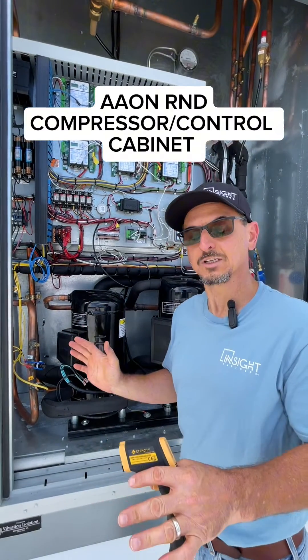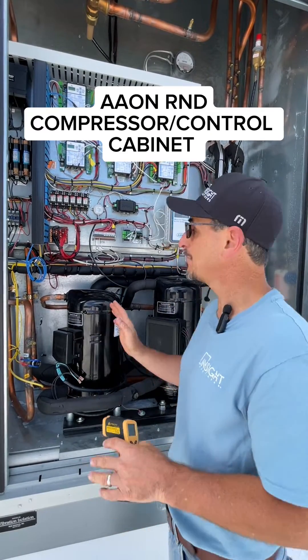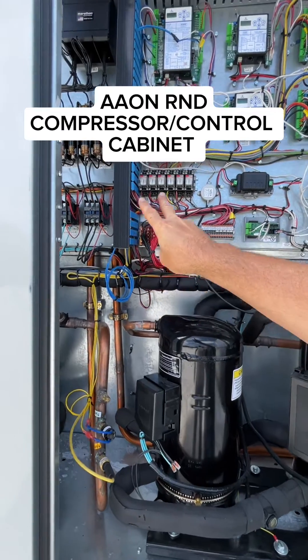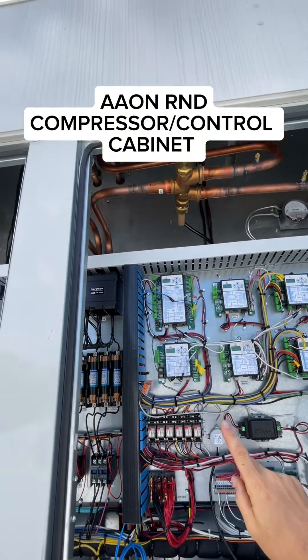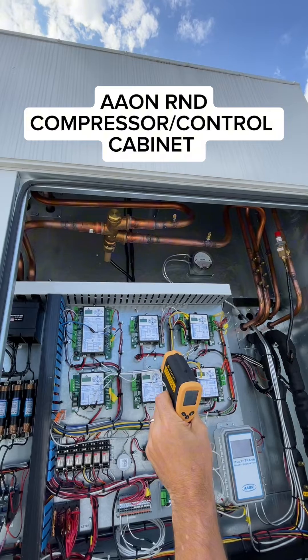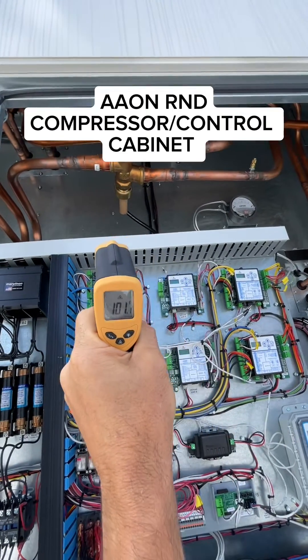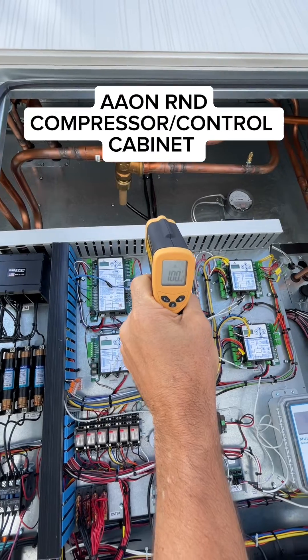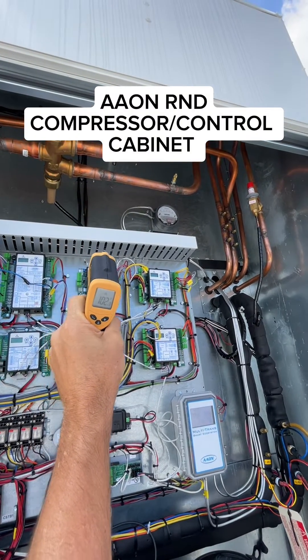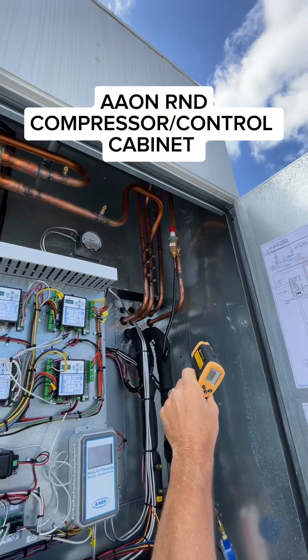The interesting thing about AAON units is most of them, especially makeup air units dealing with some type of dehumidification, have a modulating hot gas reheat valve. This is a great example — you can follow the discharge gas line. These two lines for both circuits go up behind the controls and high voltage panel area. This is the three-way valve here. You can see the temperature entering the three-way valve is about 102 degrees. Some of it goes through circuit A, which goes to the condenser coil on the top of the unit, and the other one, circuit B, goes to the modulating hot gas reheat coil, which runs all the way here and into the cabinet.